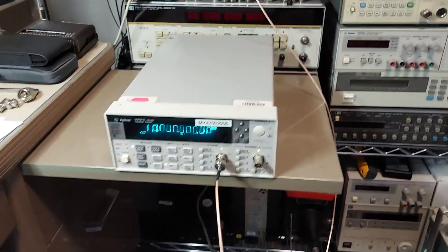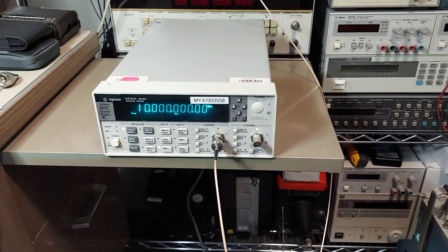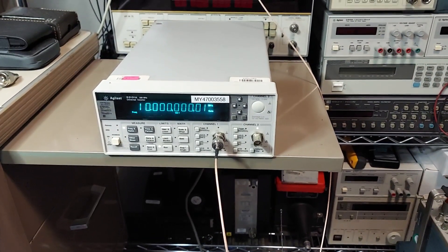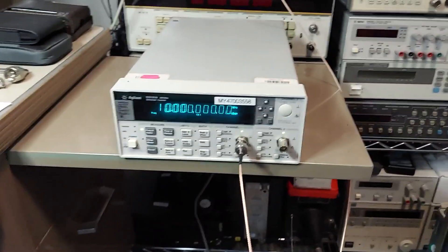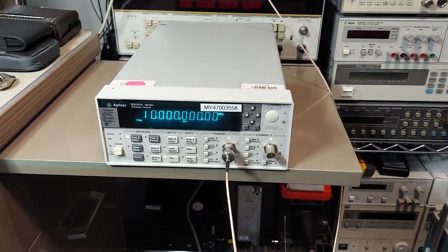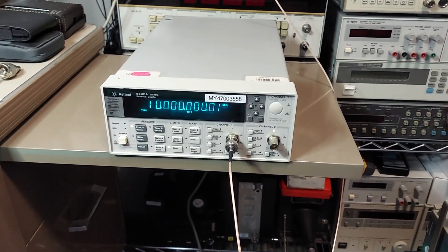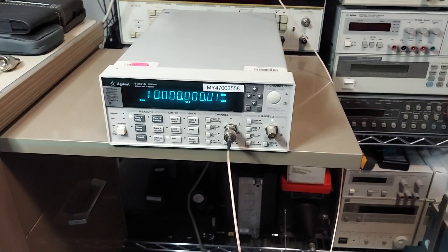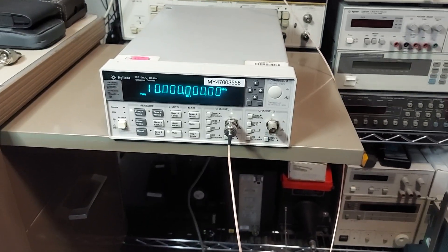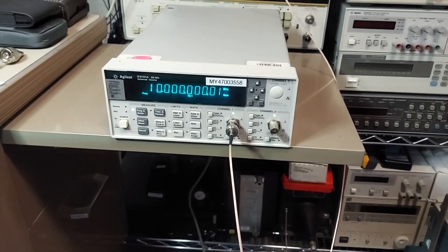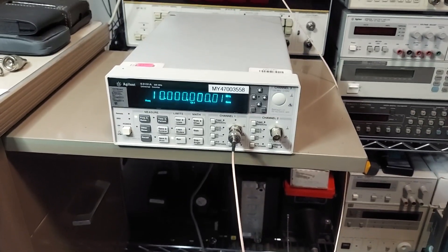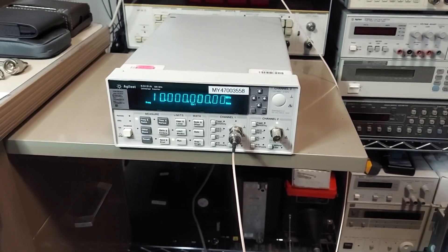That should be here next week. I've also gone through the timebase alignment procedure. You don't open the case anymore, it's all menu driven. You go in and get into the calibration menus and have it calibrate to your reference. I waited 24 hours, hooked it up to my GPS-DO, and it's done.